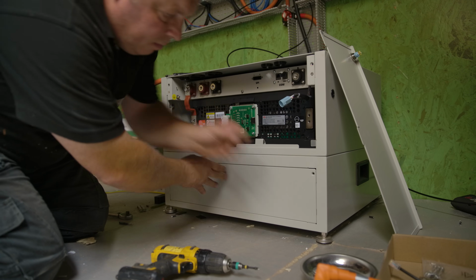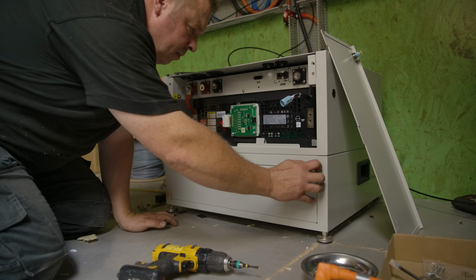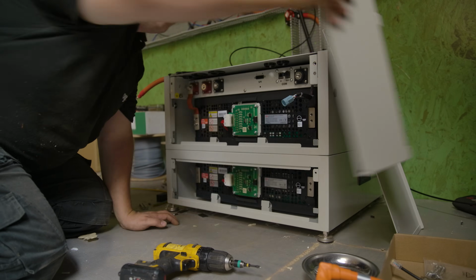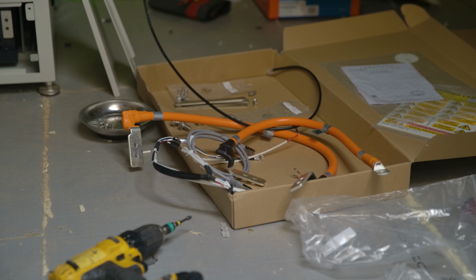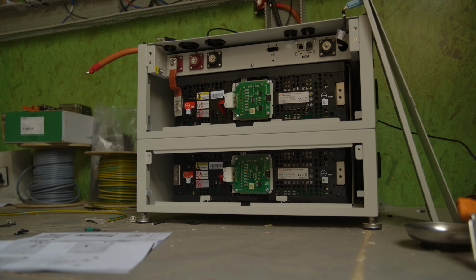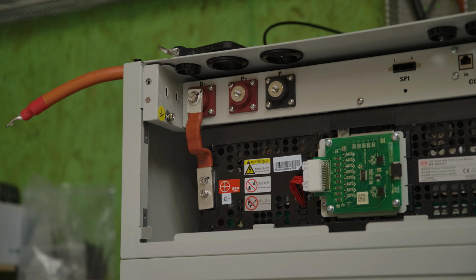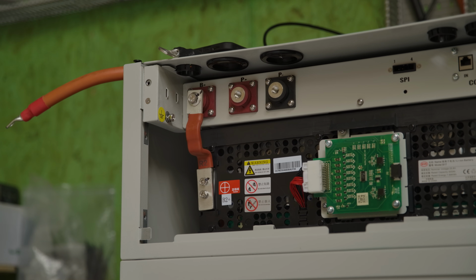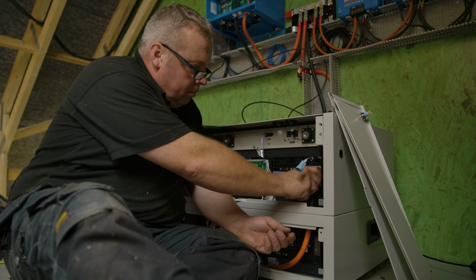Before the battery can be commissioned, Scott needs to connect the 2 24 volt batteries in series using the supplied BYD power cables. The battery bank we've chosen is from BYD, so commonly these days we would use lithium iron phosphate technology along with Victron switchgear.